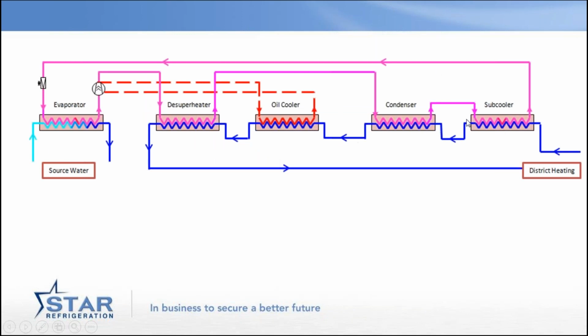So here you see the complexity simplified a little bit in a line diagram, but basically we're taking the district heating water back in to the subcooler, then the condenser, then the oil cooler, then the de-superheater. And these two are the ones where we can get heat at about 95 degrees. And so the condenser could maybe be about 78 degrees, and we blend this heat back in to get an average temperature of 80, if that's the case.